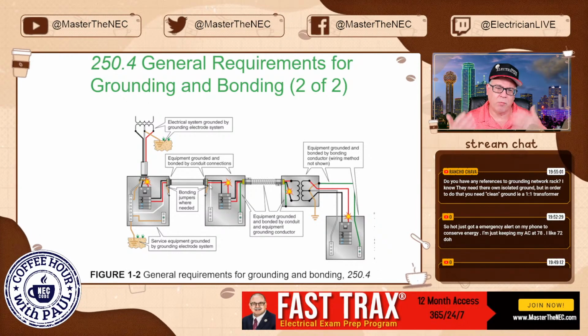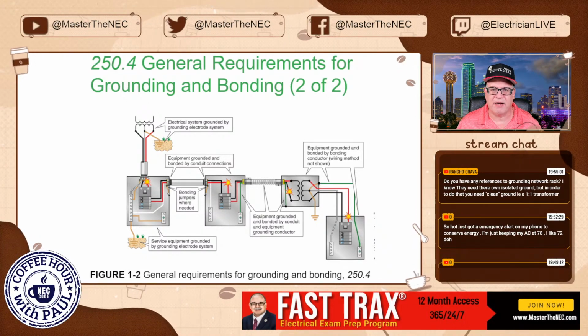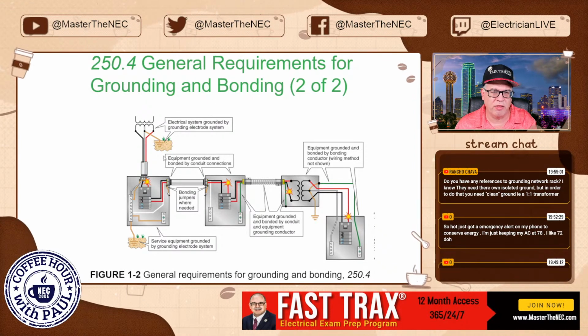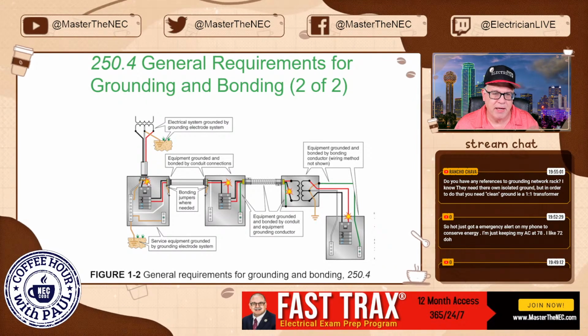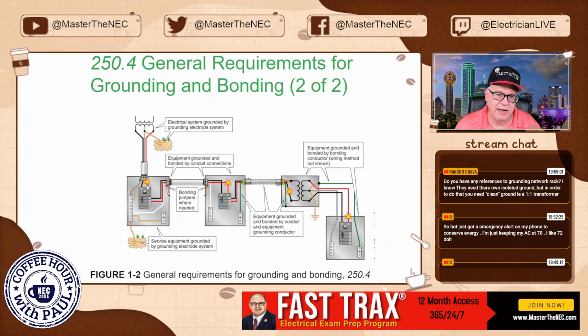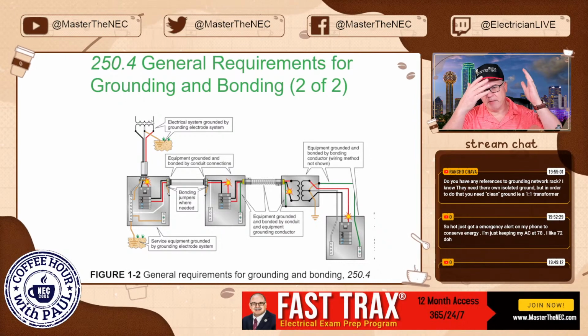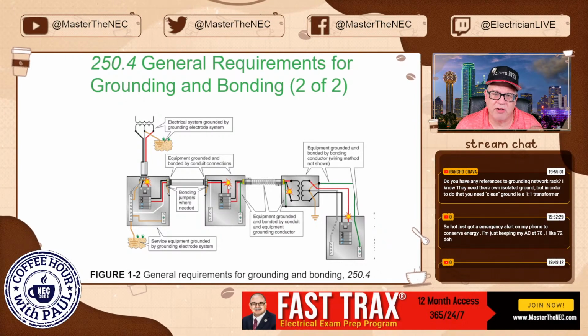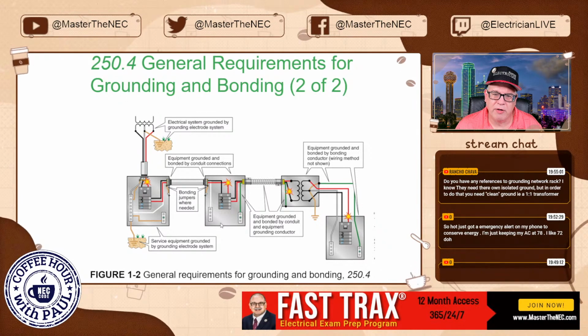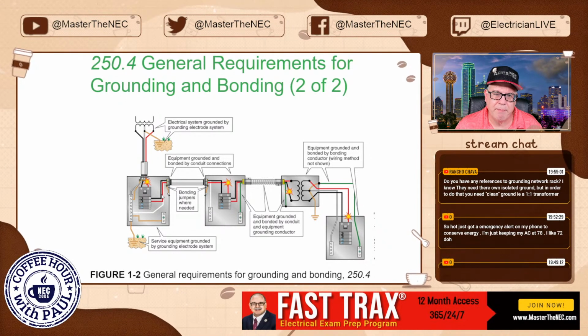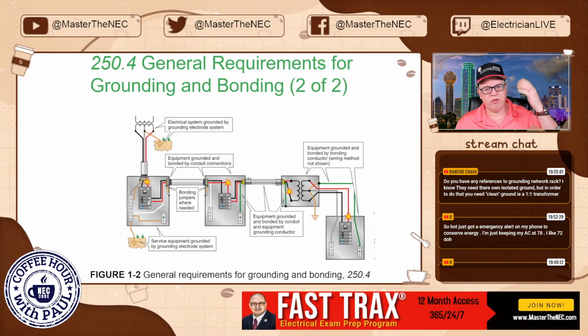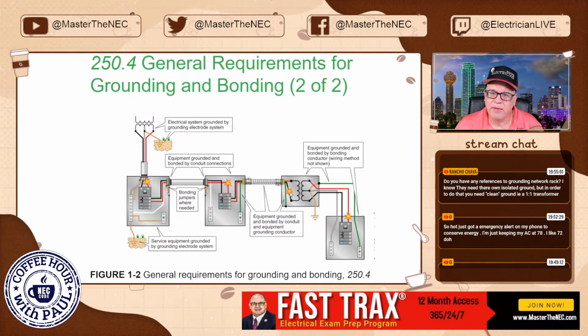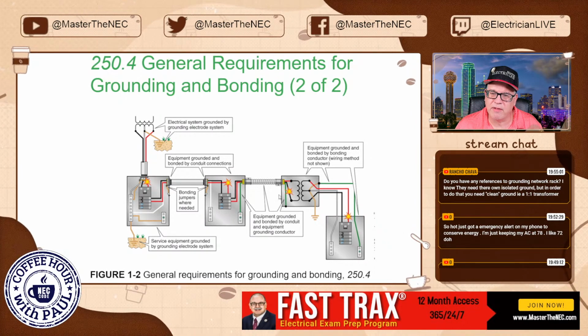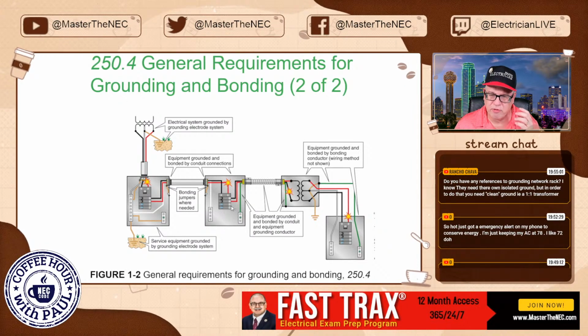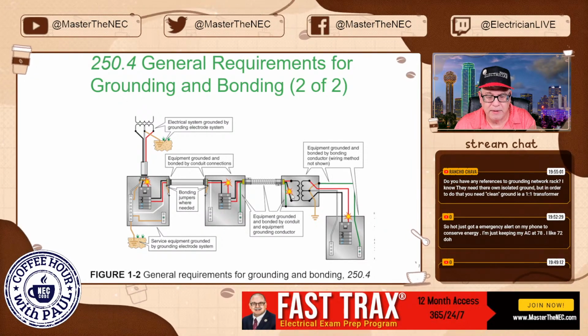But notice something here. The whole concept we're trying to do is be able to clear overcurrent protective devices. We've got this reference right here to earth. If we get a fault right here, it goes over onto the metal cabinet, comes back over here, goes back on the neutral. Okay, there you go. You've got a fault downstream here, it gets to the metal enclosure, follows its way back to the source, and clears this overcurrent protective device. Here, if you have a fault downstream right here, this is the equipment grounding conductor that's taken to the transformer, okay?